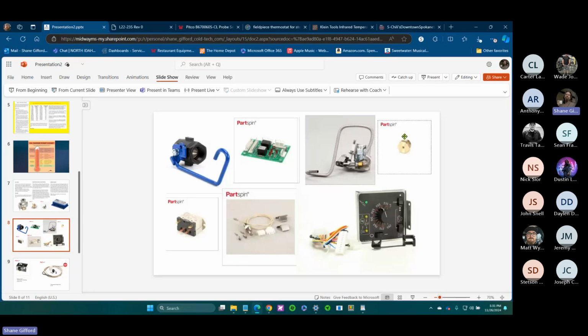So Spud, you know what a spud is, or orifice? Yep. Sweet. Those things got me really bad one time. I had a natural gas orifice on a gas furnace that we had to do an LP conversion kit on because it was not running natural gas. It was out in Malad, Idaho, and the lady had a buried tank and did not have the correct orifice for the correct gas, and it caused the inside of the heat exchanger to soot up something fierce.